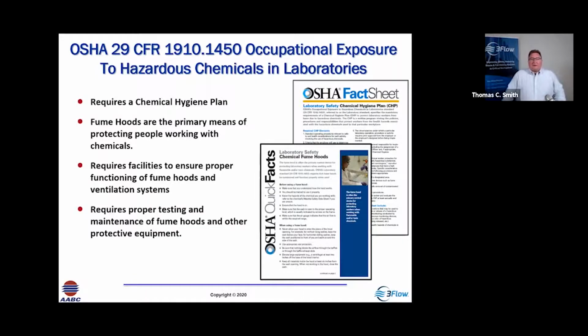So in 1991, OSHA passed 29 CFR 1910.1450, which is the lab standard, and it requires all facilities to have a chemical hygiene plan. It requires facilities to ensure the proper functioning of fume hoods and ventilation systems, and it requires proper testing and maintenance of fume hoods and other protective equipment. So it's a law. It's not an option for facilities. They must ensure the proper functioning of fume hoods. They must protect their people from overexposure. So it's an actual requirement. So we're going to focus on proper testing.